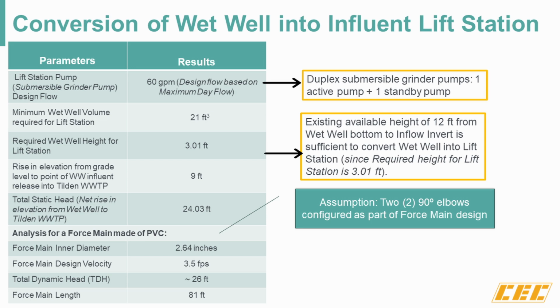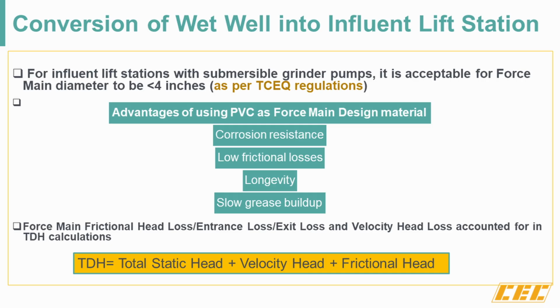So going into a few more details about the lift station. For the lift stations with submersible grinder pumps, it is acceptable if the force main diameter is less than 4 inches as per TCEQ regulations. And this exception comes into play only because we're dealing with high solids concentration in the water.